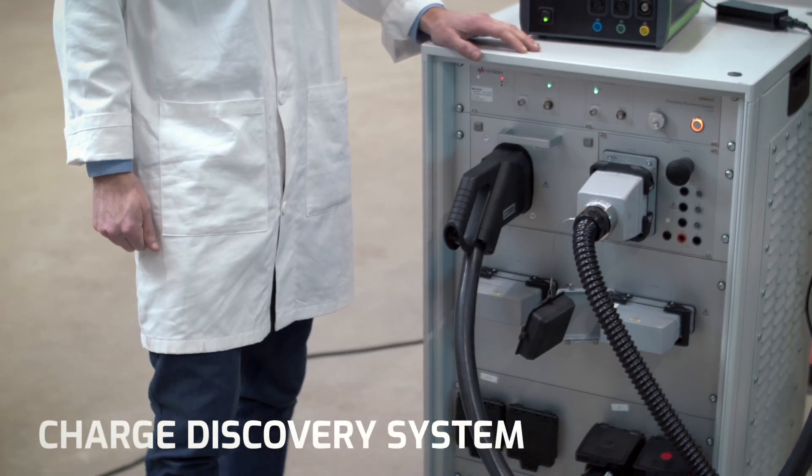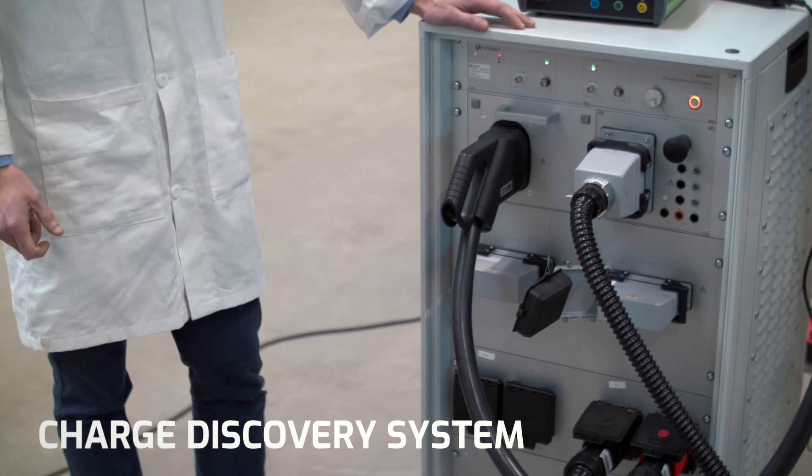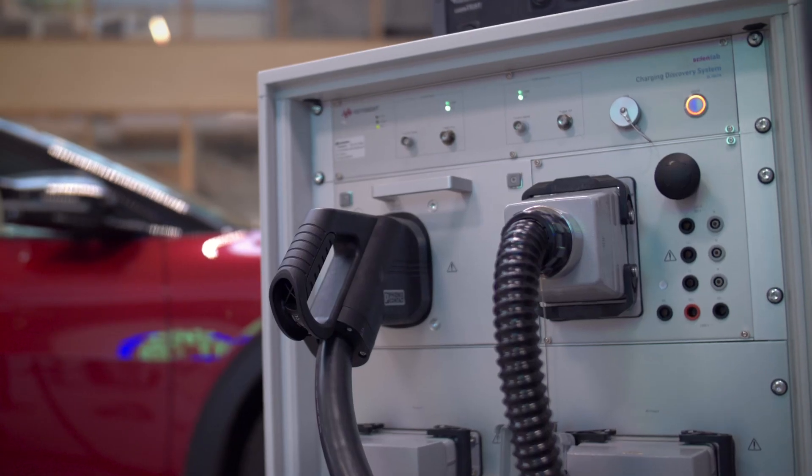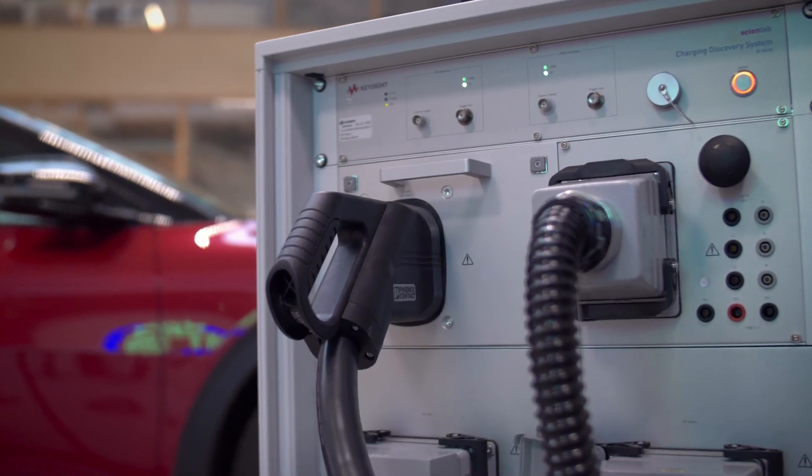This is a charge discovery system, so this emulates an electric vehicle or a charging station, and it can emulate all kinds of new types of protocols, like the ISO 15118-20 protocol, which also allows for bi-directional charging, so also giving energy back to the grid.